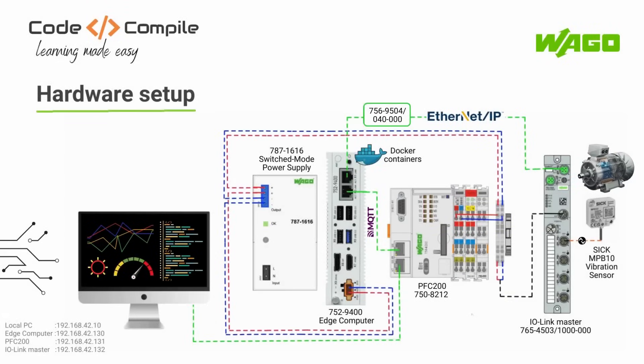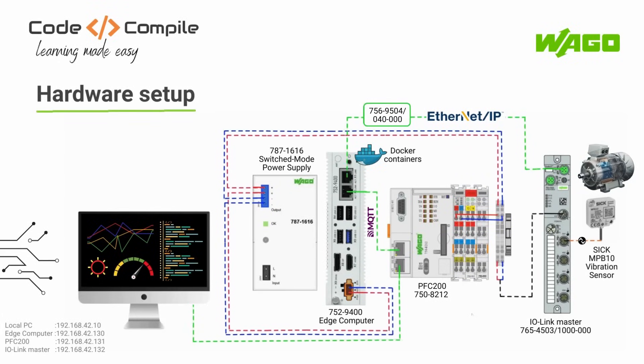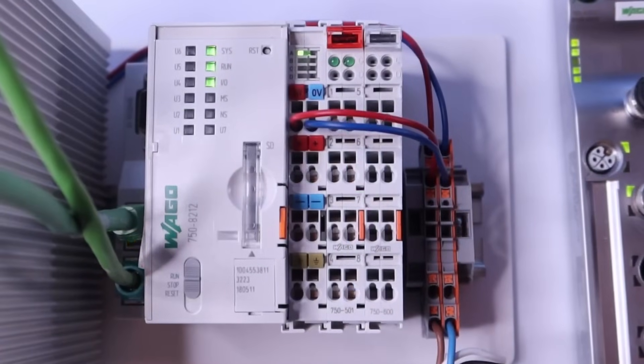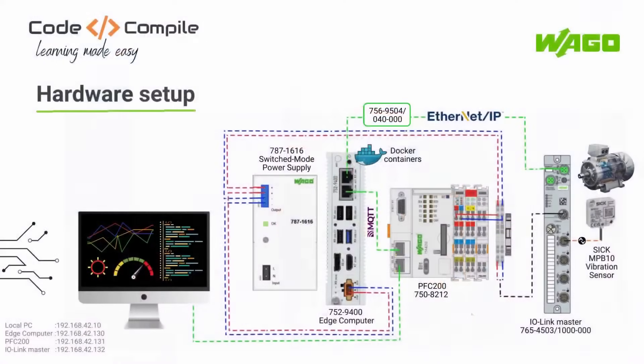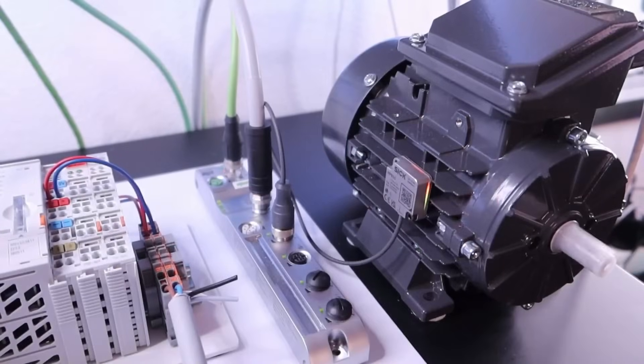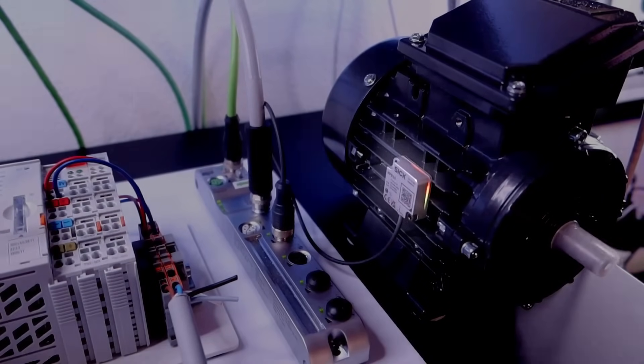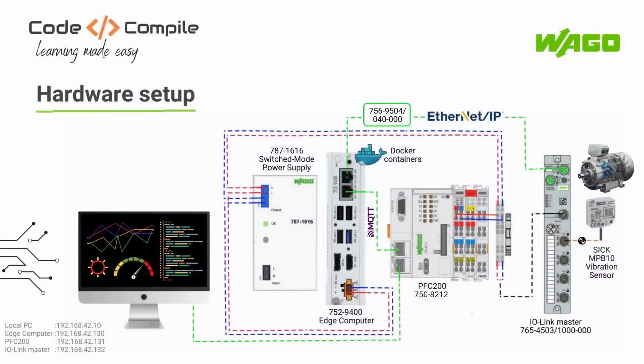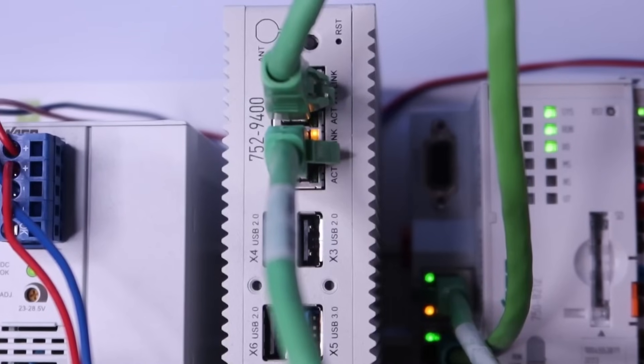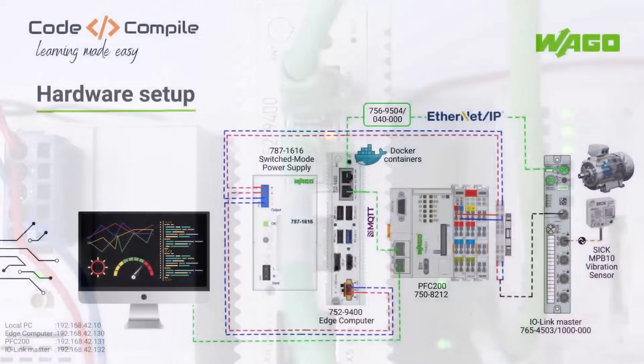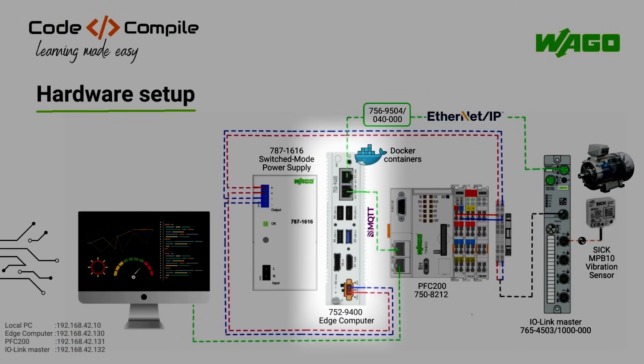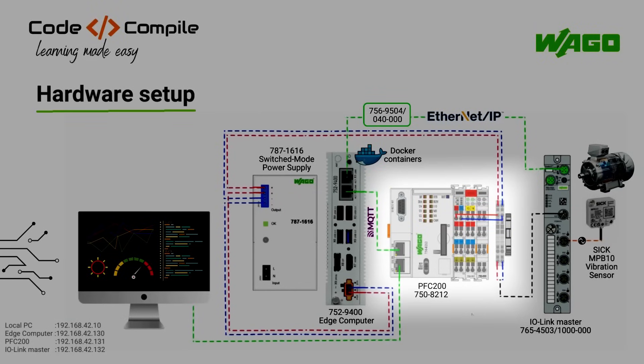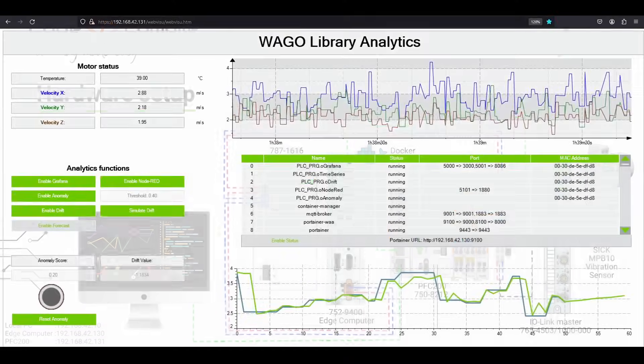For this video, I am using several hardware and software tools, starting with PFC 200, which is loaded with WAGO Library Analytics based on Codesys. This PFC 200 is getting the vibration data from my industrial motor, which is equipped with a vibration sensor via an IO link master. The vibration data is being sent to WAGO Edge computer, which is preloaded with machine learning models running on Docker containers. These machine learning models can be installed on the Edge computer using a single setup file. These machine learning models analyze the data and send results back to PFC 200 to trigger alarms or to display data on the WebVisu.